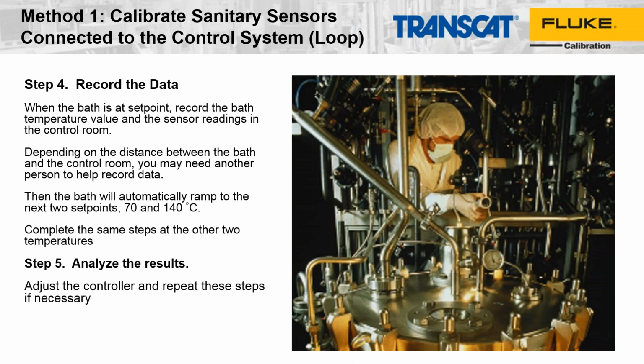So then step 4, when the bath is at the set point, this is where you take the data, and you will have to look at the controller display and compare that with the display on the 7109A. And sometimes the control display may be off in a control room, and you may have to have a second person help you out with that, and so you can take that data. And then you just continue these steps through the other temperature points.